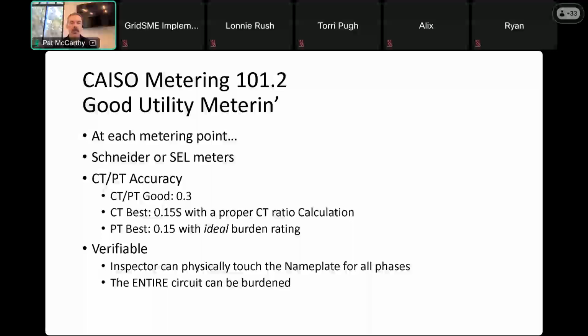Another example of increased accuracy requirements from ANSI: CAISO has long used the 0.3 error tolerance, or 0.3 accuracy class, for current transformers, that's the CT, and potential transformers or voltage transformers, that's a PT. That's a good standard. However, ANSI has since come out with 0.15, which is half the allowable error, so twice as accurate. And the S that I have on the screen there is extended range.